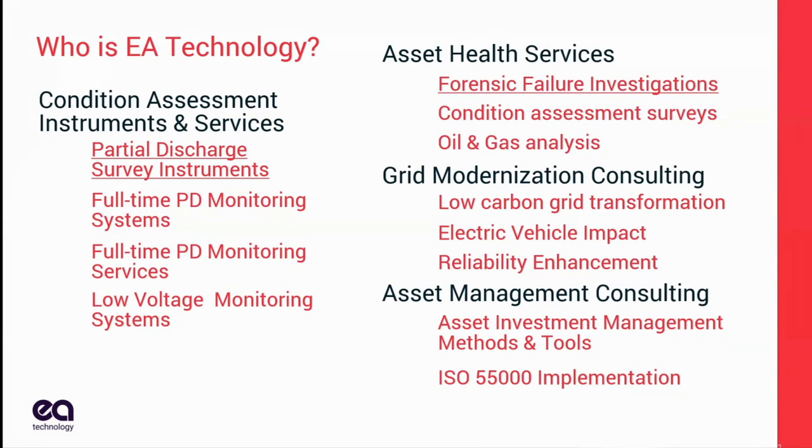One, we maintain a large, highly qualified forensic failure lab. So customers from around the world send us cable terminations that might have failed, or switchgear that failed, or have us go out on site to look at a transformer. And we do a lot of this work, and that allows us a lot of insight into how assets fail. And that's part of this discussion today, with some of the results of what we've gotten analyzed.